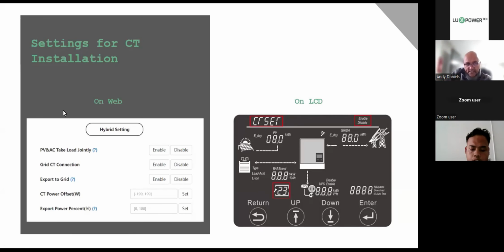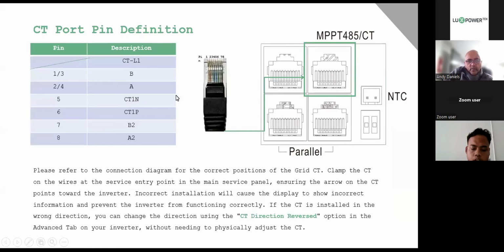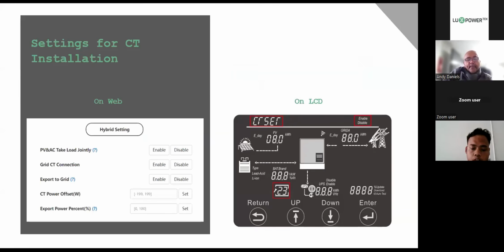And then your CT offset, the reason we put this in here, and it's in watts, okay? These CTs here, this one that we supply with the machine, we do not manufacture it. It's a third-party supplier. We can't control the accuracy of the CT. So if you connect the CT to your machine and you don't want to export, but you notice that there's a small variance, like maybe 50 watts or 100 watts, it's still pushing out, it simply means that the CT is under-reading. Then you can offset it here.